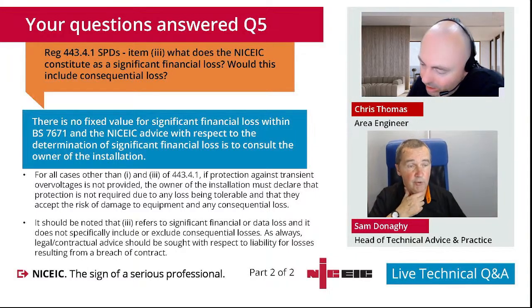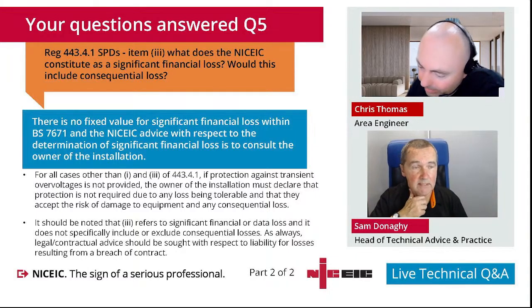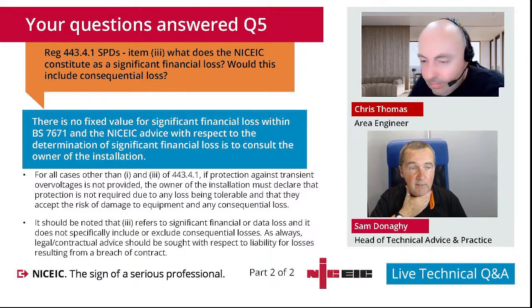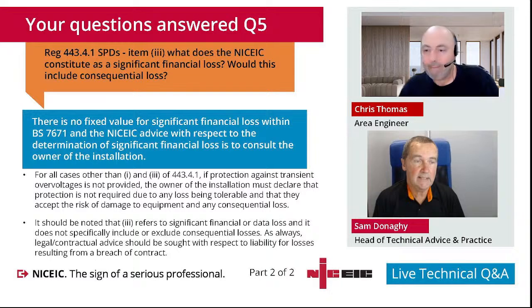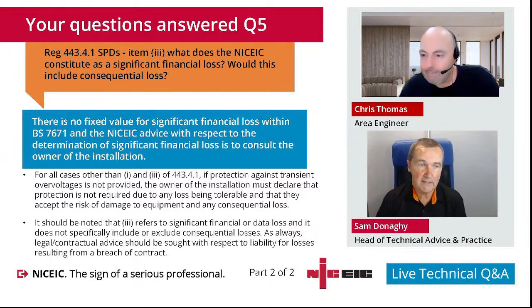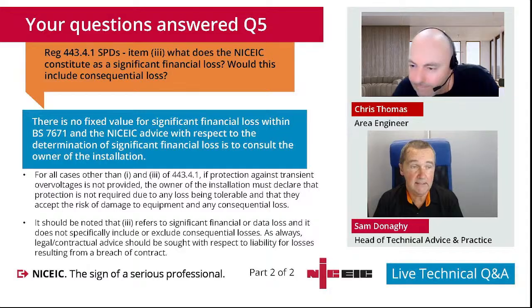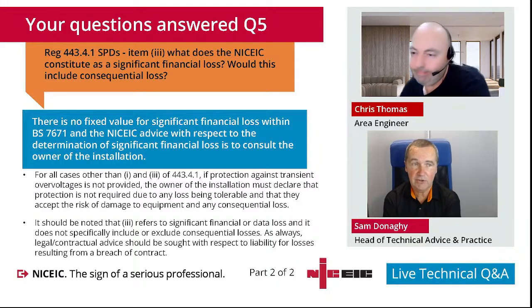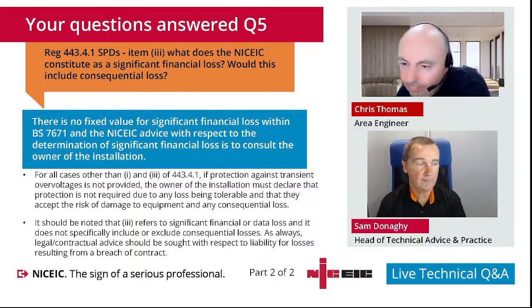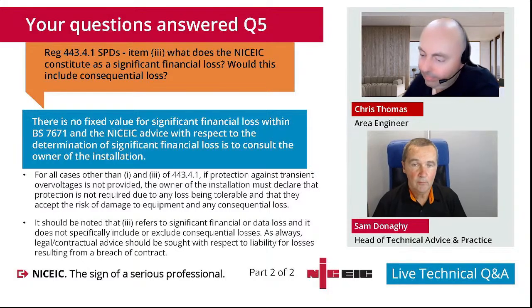Yeah, that's a really good point in terms of if they are considering installing it in containment, then not only have you got to consider the de-rating factor of the containment, but like you say, is it a grouping issue as well? Because if we're going to put other cables in there, then effectively they act as heaters to each other, which again has a detrimental effect on the cable's capacity to disseminate that extra heat. So yeah, we'd be looking at a further reduction in current carrying capacity if it was in containment and with other cables.